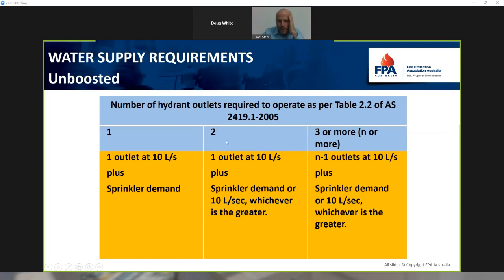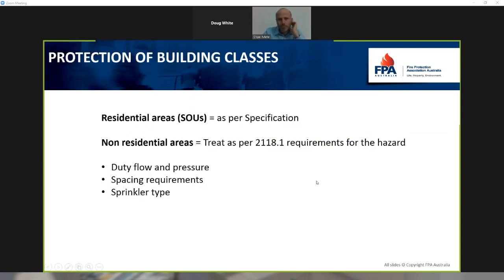It tells us that for the sprinkler system, we can have 1 hydrant outlet's worth, in other words 10 litres a second, used to supply our sprinkler system. So that's a concession. We still build our water supply for only 2 hydrant outlets running, 20 litres a second, and we use our sprinkler demand from that 20 litres a second. It's not included above. It's not in addition to. And the same applies if you need 3 hydrants, then you can still have 1 hydrant outlet supplying the sprinklers.